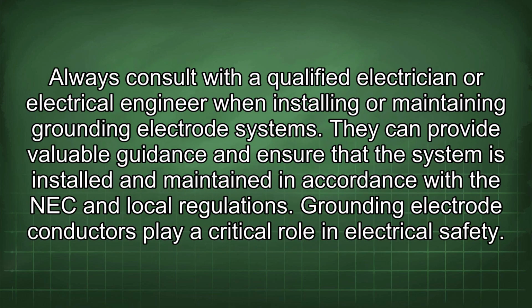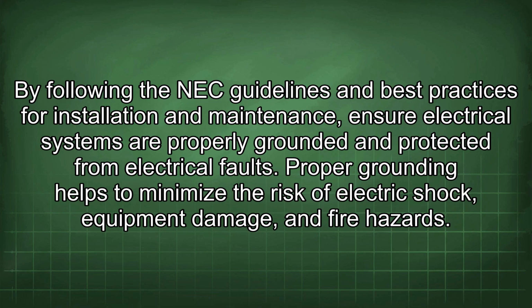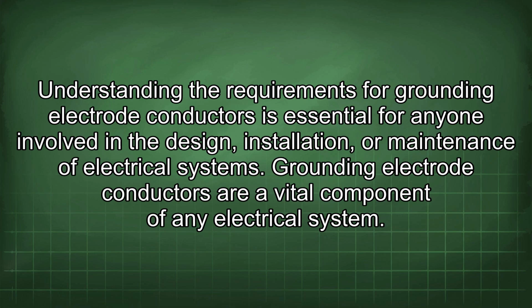Always consult with a qualified electrician or electrical engineer when installing or maintaining grounding electrode systems. They can provide valuable guidance and ensure that the system is installed and maintained in accordance with the NEC and local regulations. Grounding electrode conductors play a critical role in electrical safety. By following the NEC guidelines and best practices for installation and maintenance, ensure electrical systems are properly grounded and protected from electrical faults. Proper grounding helps to minimize the risk of electric shock, equipment damage, and fire hazards. Understanding the requirements for grounding electrode conductors is essential for anyone involved in the design, installation, or maintenance of electrical systems.